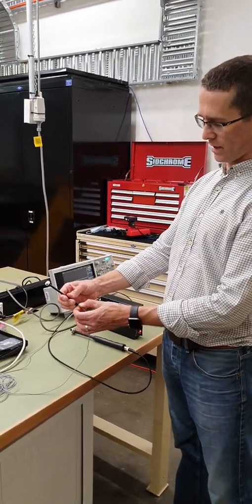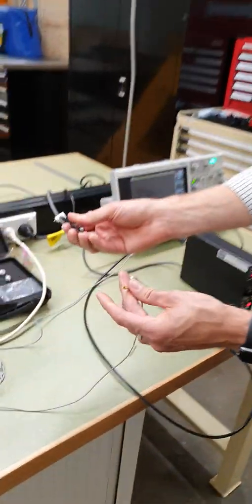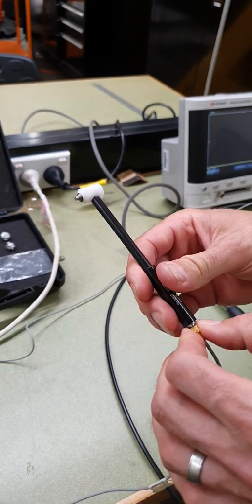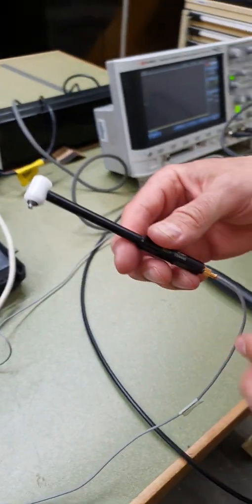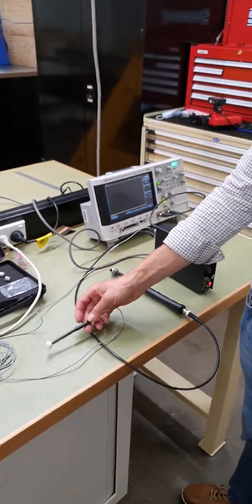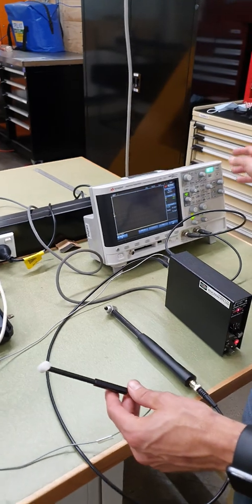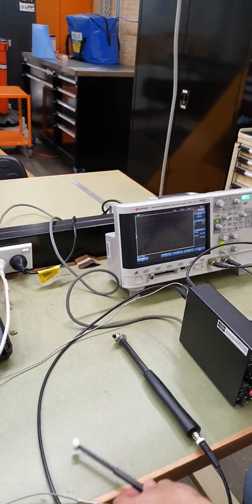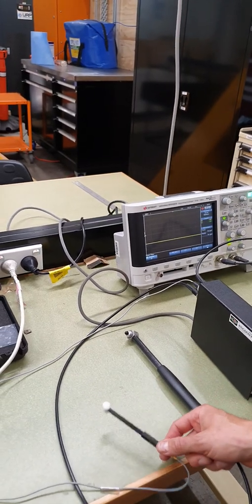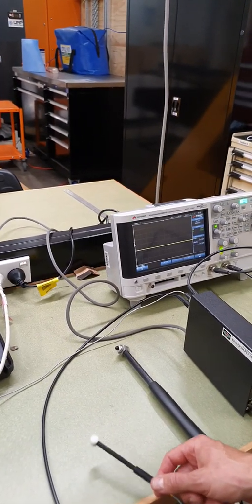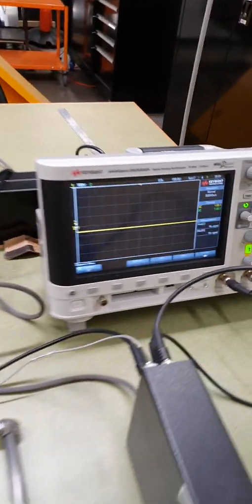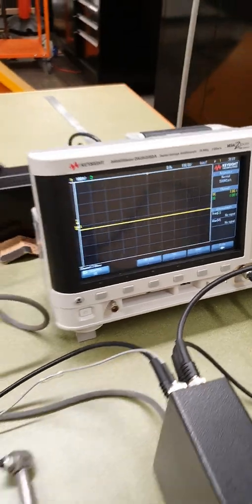It's essentially the same in terms of cabling, which is we connect to the micro force hammer in the same way. Embedded within this end is a force transducer which is essentially an accelerometer without the mass on it. When we connect this with signal conditioning to the electronics, you can see that as I impact that structure we get little impulses. It might not come across properly in this video because they're very quick depending on the frame rate, but I'll show it in more detail in a moment.